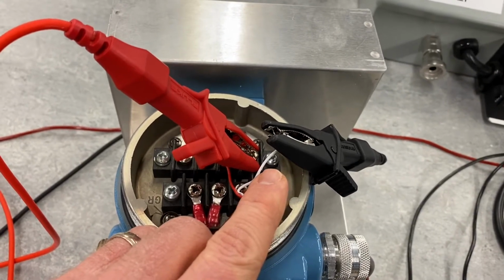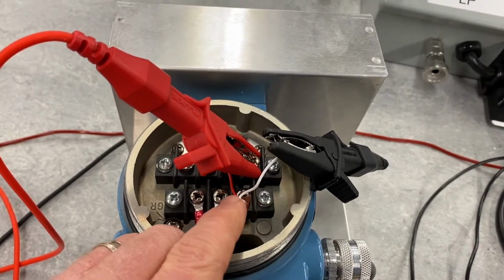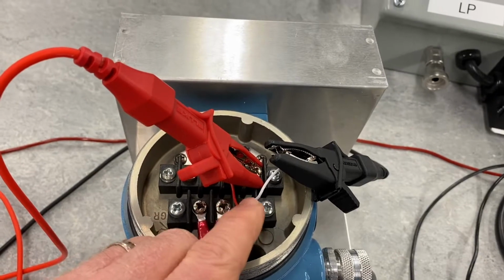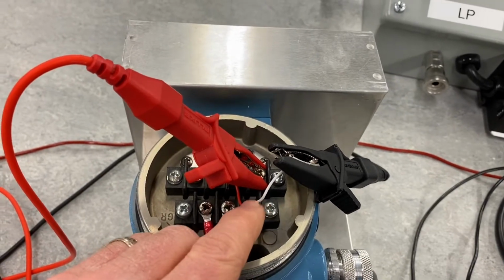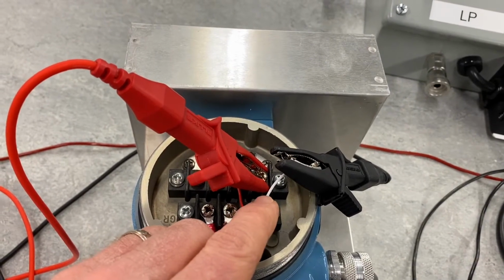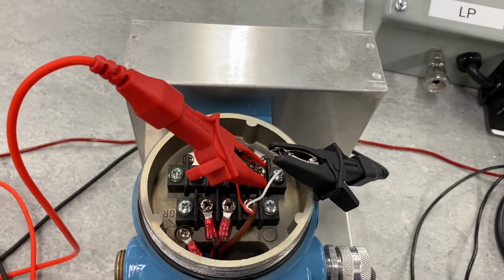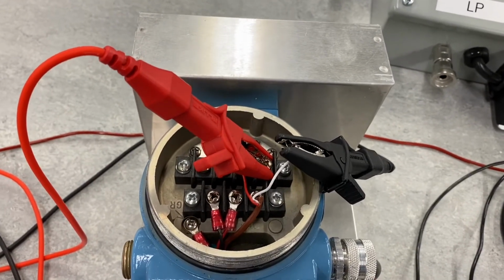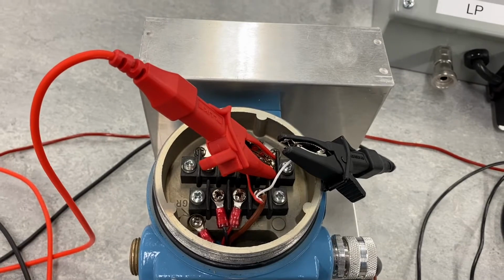So thermocouples are kind of an anomaly. The red lead on a thermocouple is always negative, and the other color, the identifier of the thermocouple, which for this type J is white, is the other lead. So red is always the negative lead on a thermocouple.